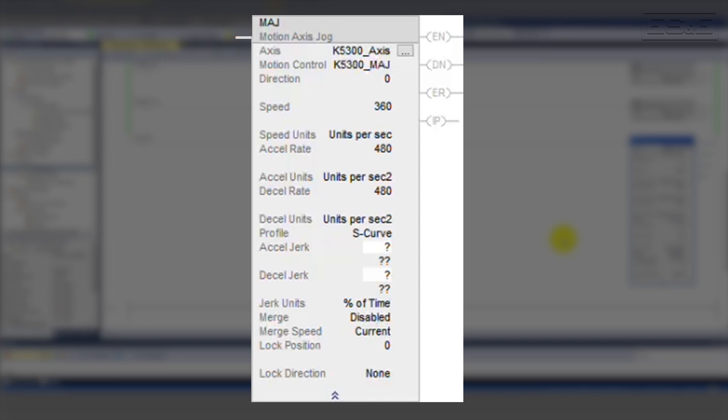For the profile field, select S-curve from the dropdown. This will activate the rest of the jerk fields for this instruction. If profile is set to trapezoidal, then the remaining jerk fields will be ignored. Now we can select the jerk rate we used in the profile calculations — enter 50 for 50% of time. As with Decel rate, the Decel jerk is unimportant for this particular move, so we can just match the Accel jerk.